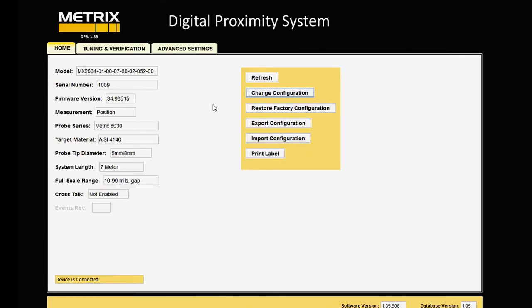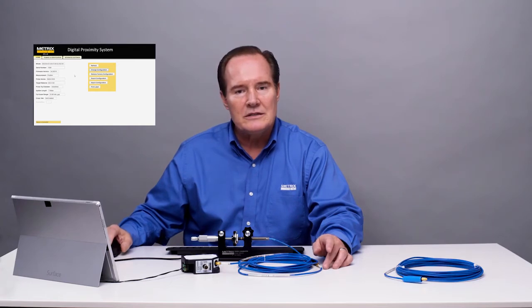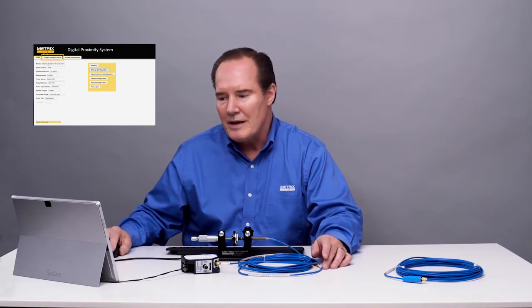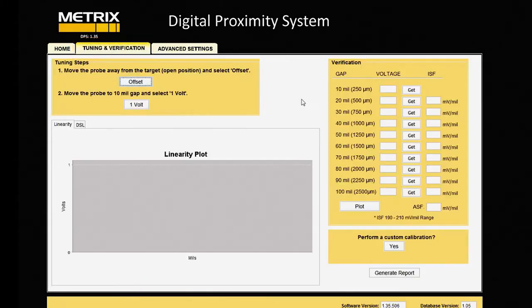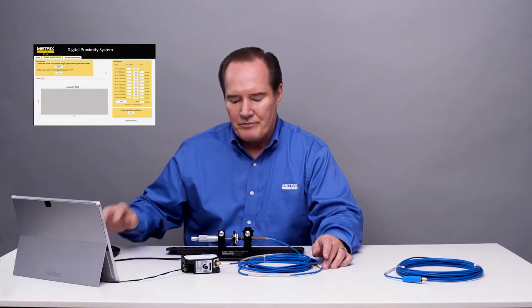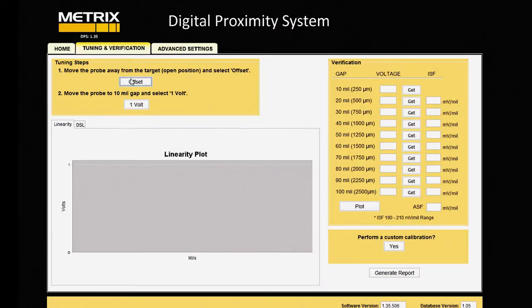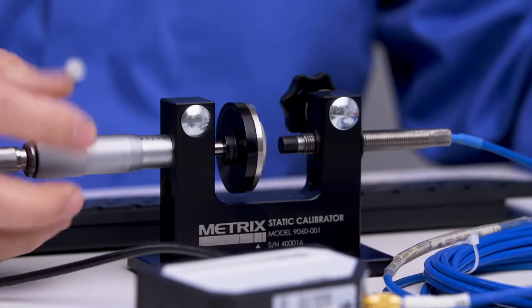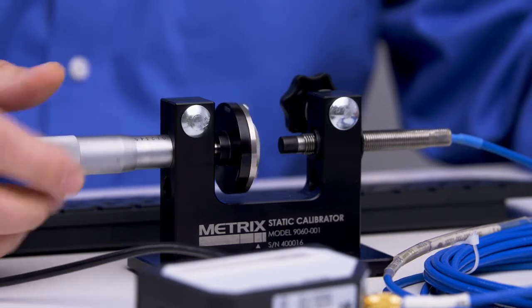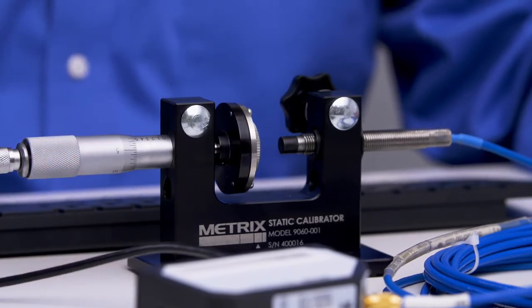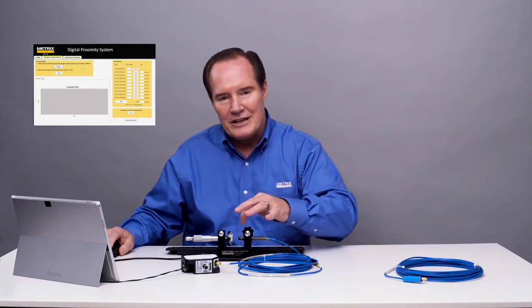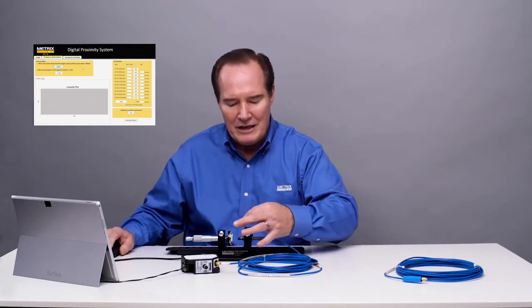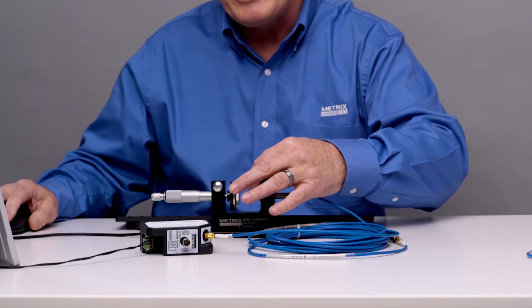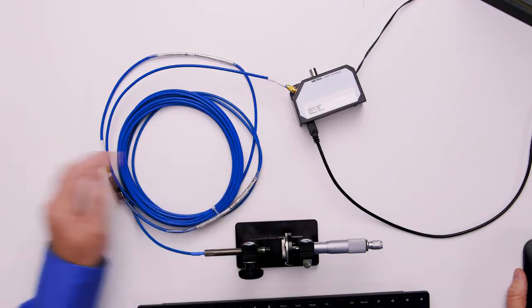All right, so I've got this system. Let's go ahead and do a tuning and verification step, and let's just see how it works. So I've reset it for 7 meters, but I want to go through this tuning step just to make sure I've got a matched system. So what I'll do is I'll open up the clearance here to over 12 millimeters, more than a half an inch. Make sure I don't have any real electrical connectivity between the radio frequency signal emanating from the probe tip to the target material.